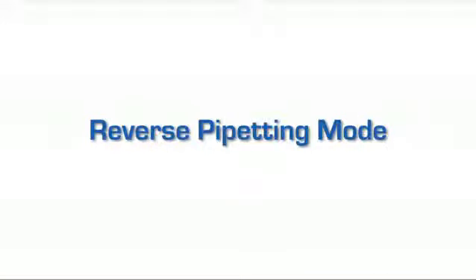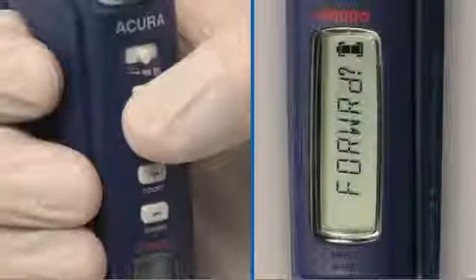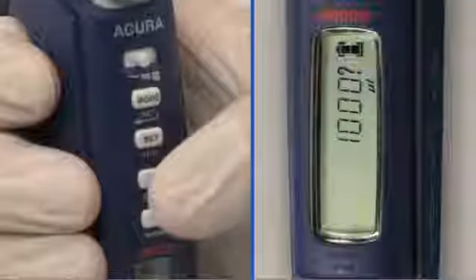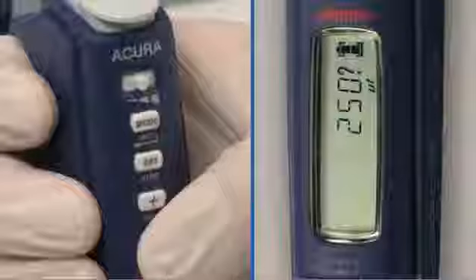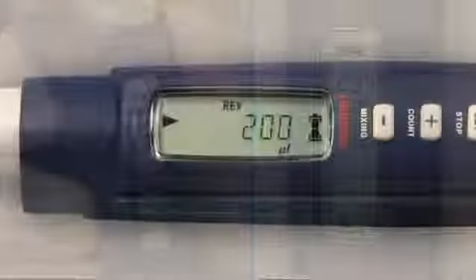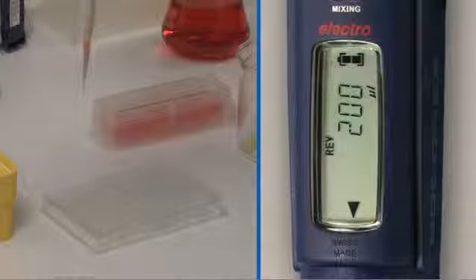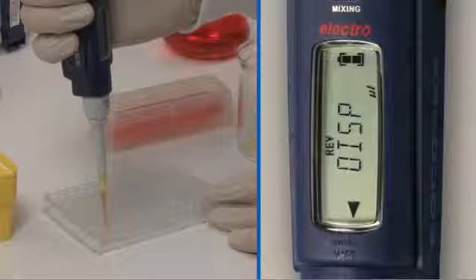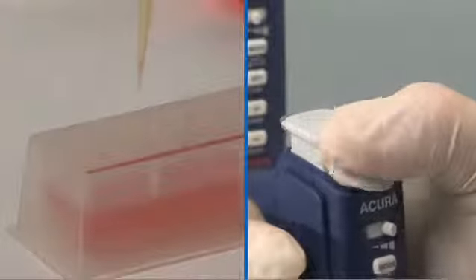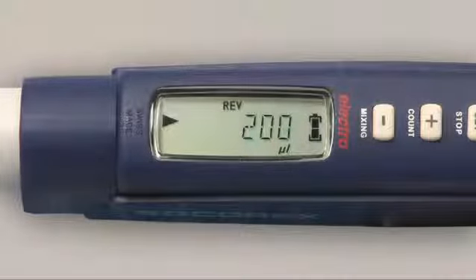Reverse mode corresponds to an aspiration in excess, followed by the dosing of a set volume. It also enhances reproducibility below 20 microliters and is especially recommended for viscous and foaming liquids. Press Mode several times until the display shows Reverse. Press Set to validate. Press the plus/minus keys to display the desired volume. Press Set again to validate. The display shows the selected mode and volume. The instrument is ready to aspirate in reverse pipetting mode. Aspirate the liquid, and the display shows it's ready to distribute. After distribution, the display shows Purge. To eliminate the excess liquid, double-click on the Start button. The display shows it's ready to aspirate again.